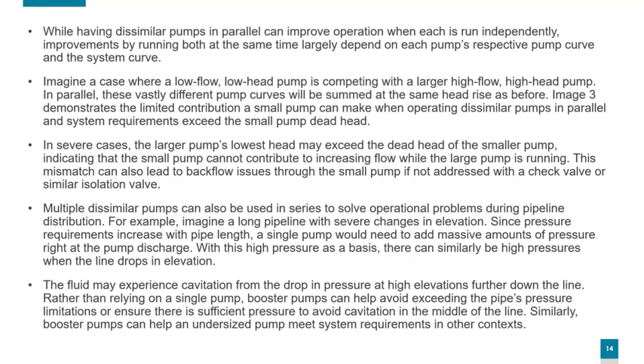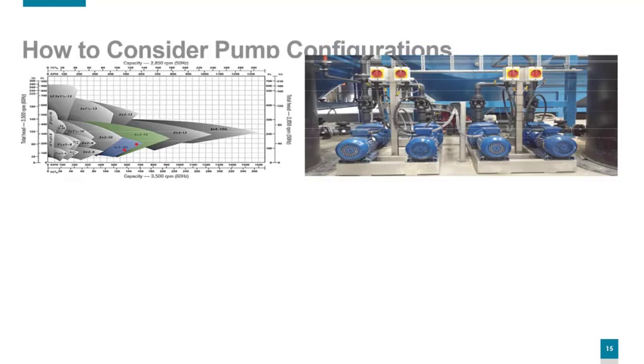Rather than relying on a single pump, booster pumps can help avoid exceeding the pipe pressure limitations or ensure there is sufficient pressure to avoid cavitation in the middle of the line. Similarly, booster pumps can help an undersized pump meet system requirements in other contexts.